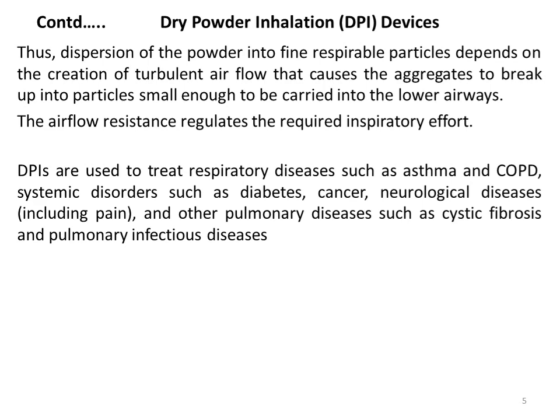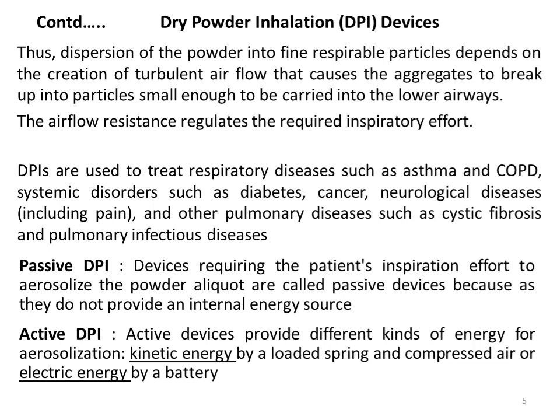DPIs are also used for other systemic disorders, for example diabetes and cancer. DPI devices may be categorized into active DPI and passive DPI. Passive DPI devices require the patient's inspiratory effort to aerosolize the powder, as they do not provide an internal energy source. Active devices provide different kinds of energy for aerosolization — for example, kinetic energy by a loaded spring or compressed air, or electrical energy by using a battery.